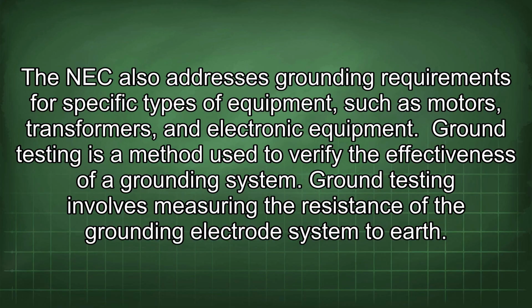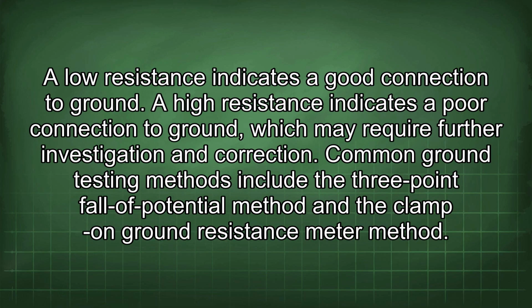Ground testing is a method used to verify the effectiveness of a grounding system. Ground testing involves measuring the resistance of the grounding electrode system to earth. A low resistance indicates a good connection to ground. A high resistance indicates a poor connection to ground, which may require further investigation and correction. Common ground testing methods include the 3-point fall of potential method and the clamp-on ground resistance meter method.